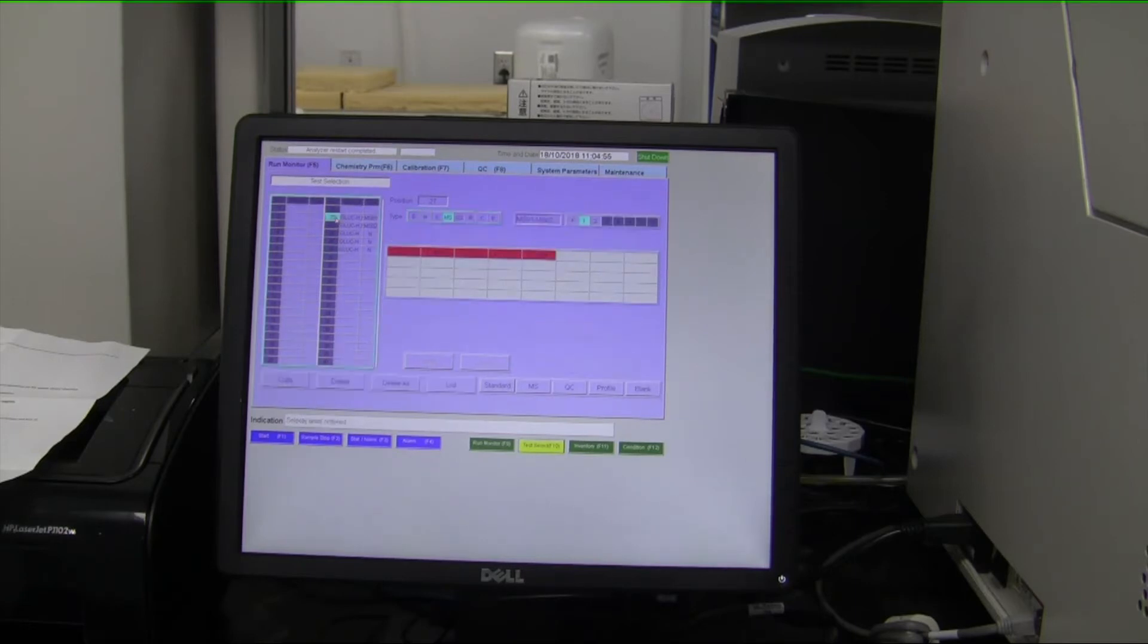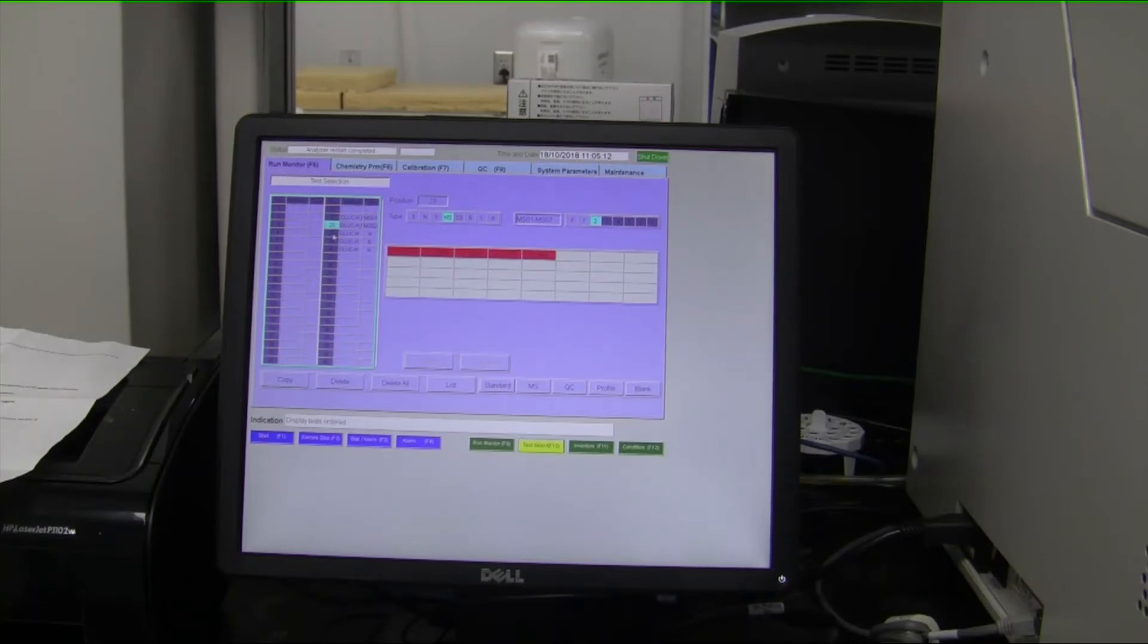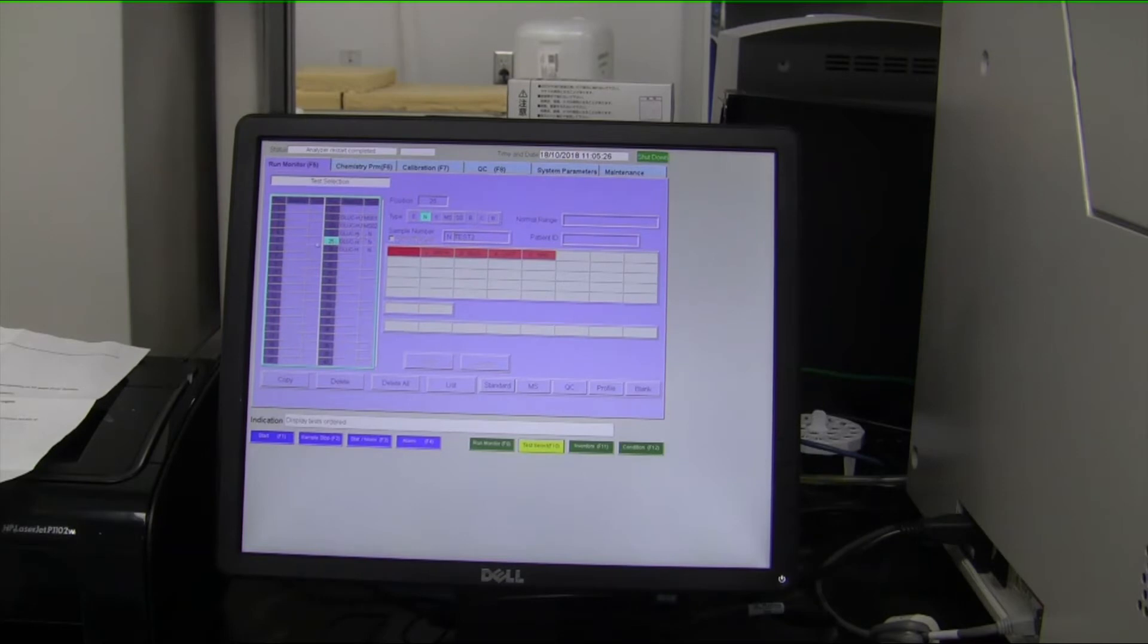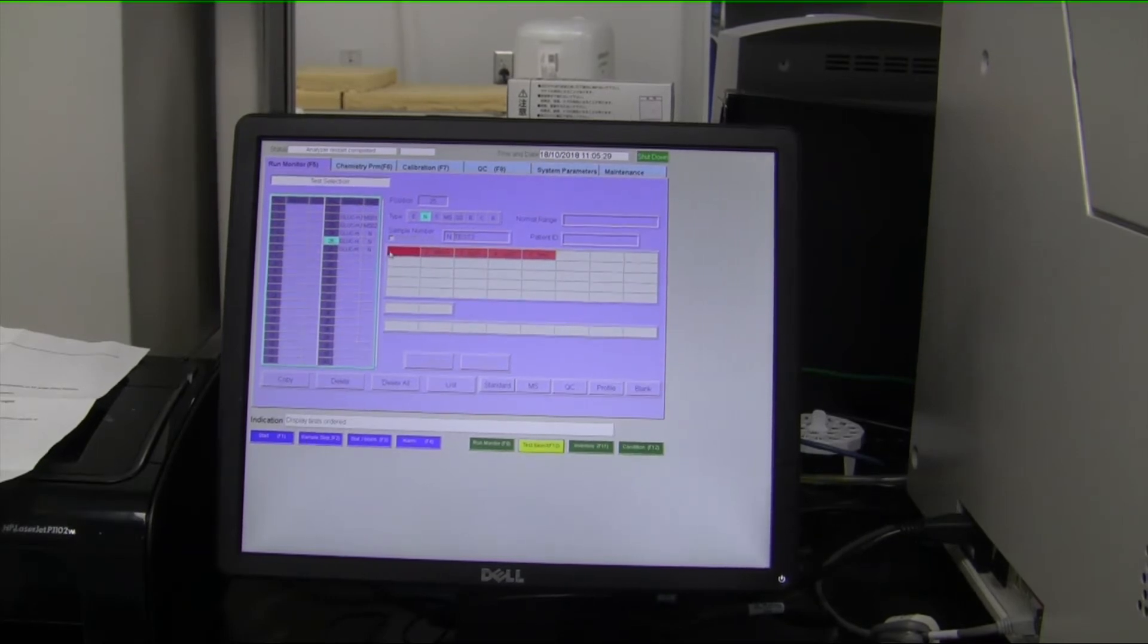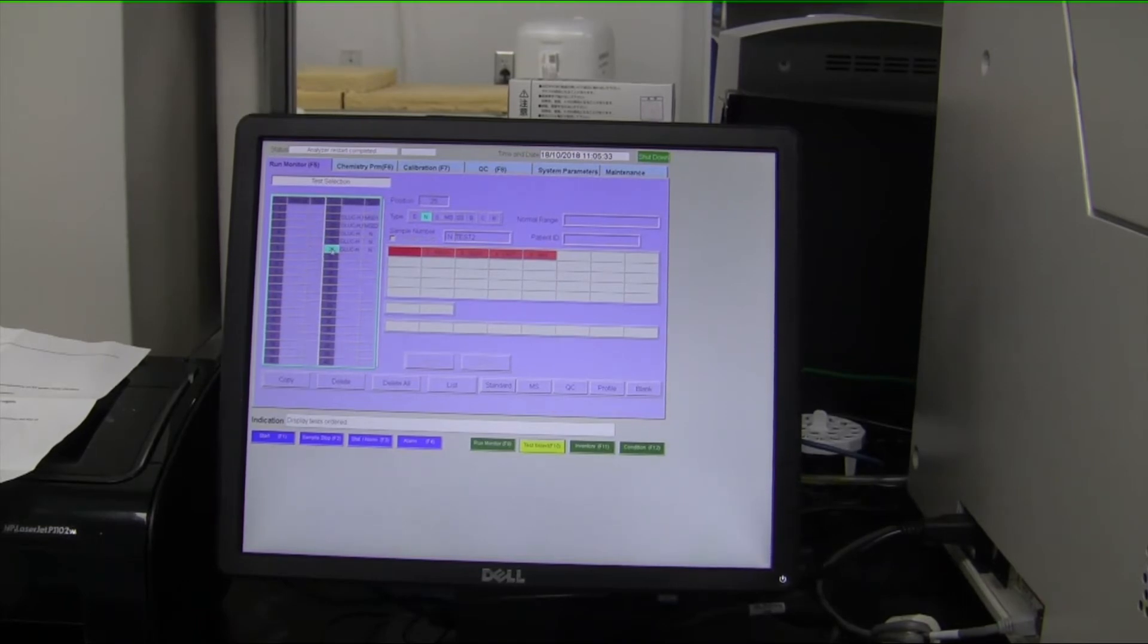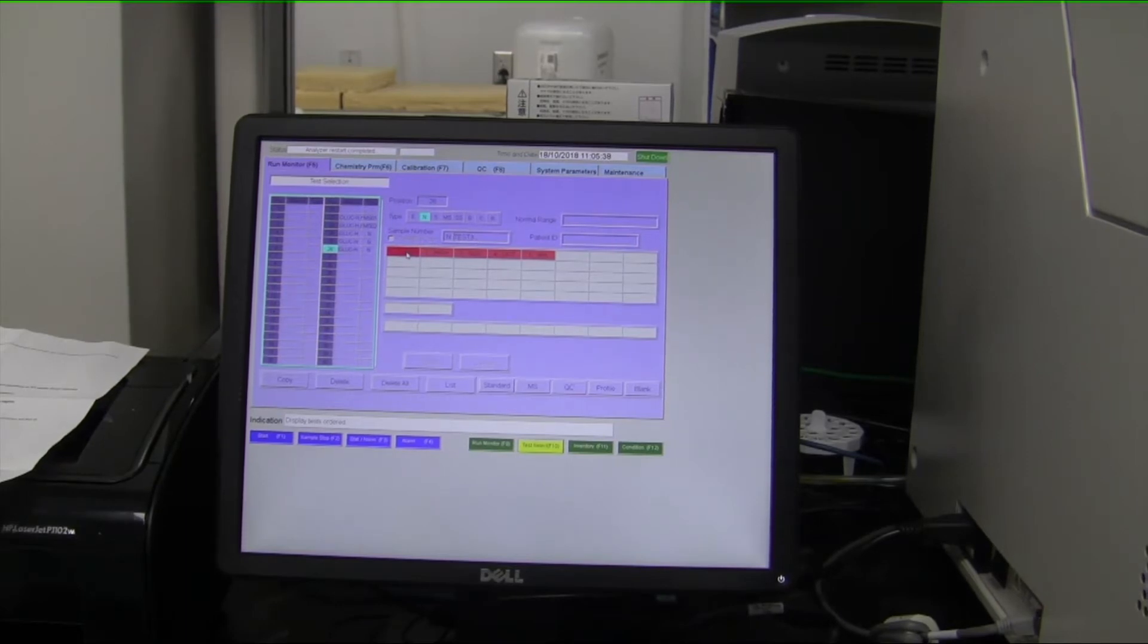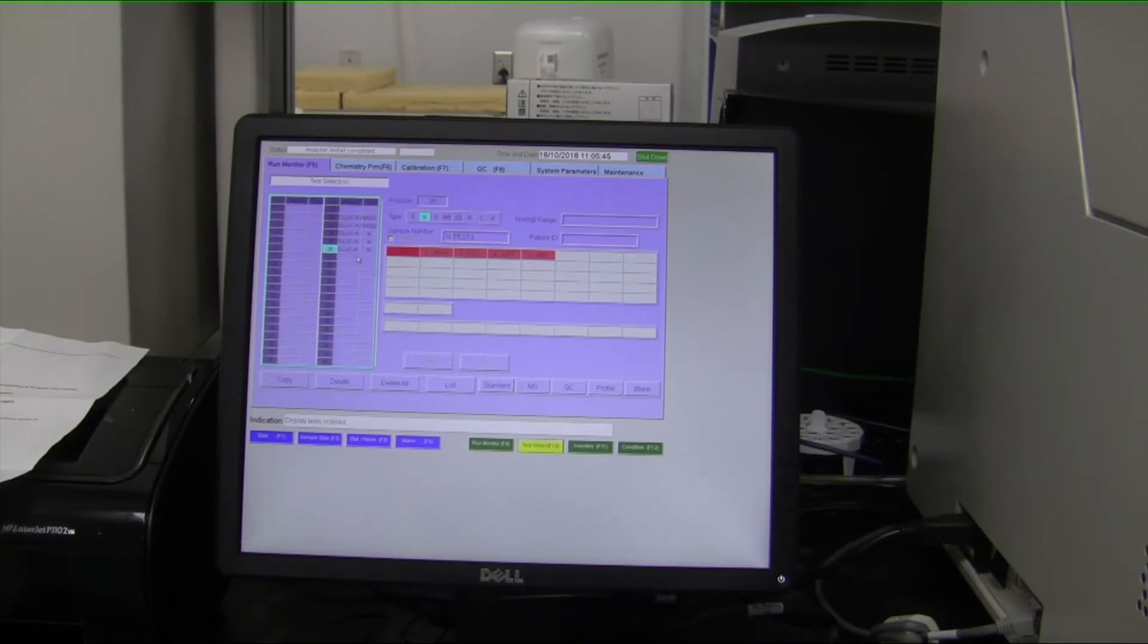So again, in position number 22, for example, we have a calibration—a multi-calibration—so that's going to calibrate multiple metabolites that are on board. You have the zero point and then you have the calibrator material. So again, position number 22 is water, position number 23 is going to be the calibrator material, and then positions number 24, 25, and 26 are going to be samples of unknown concentration—the normal sample type—and they're going to be tested for glucose. This position is called test number one, then it automatically named the next position test number two, and we select glucose to be the metabolite to be tested. And then in the next position we have test number three as the sample name, going to be run for glucose.